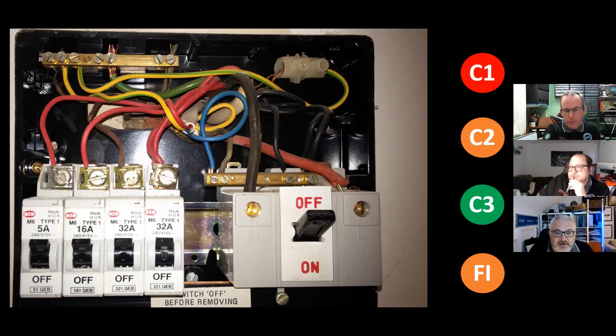Yeah, the line has already got exposed copper on it, just to the top above there, so that insulation is degrading and disintegrating already. If you follow the 32 amp VIR up, it goes left just when it goes behind the red. After that, there's a bit of exposed there, so there is damage to that.